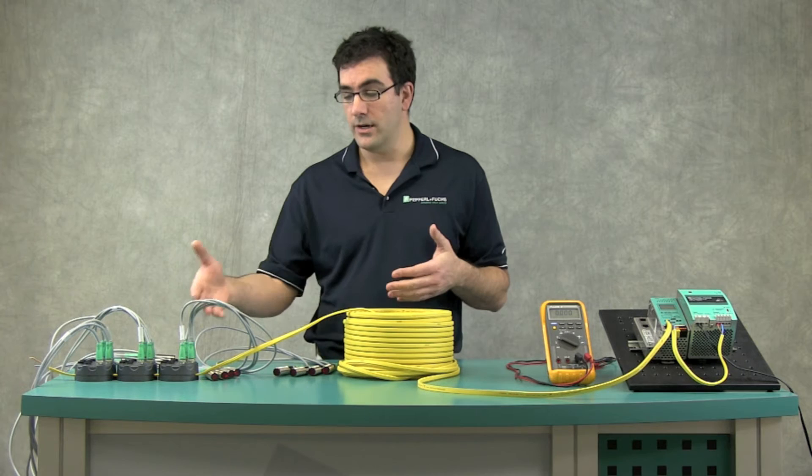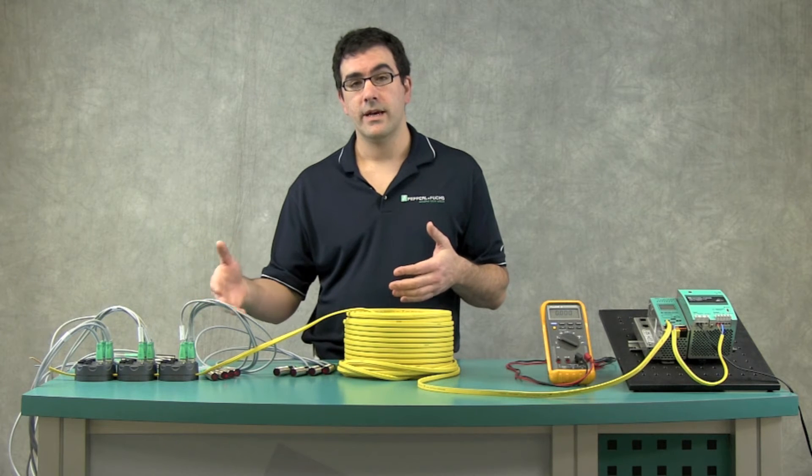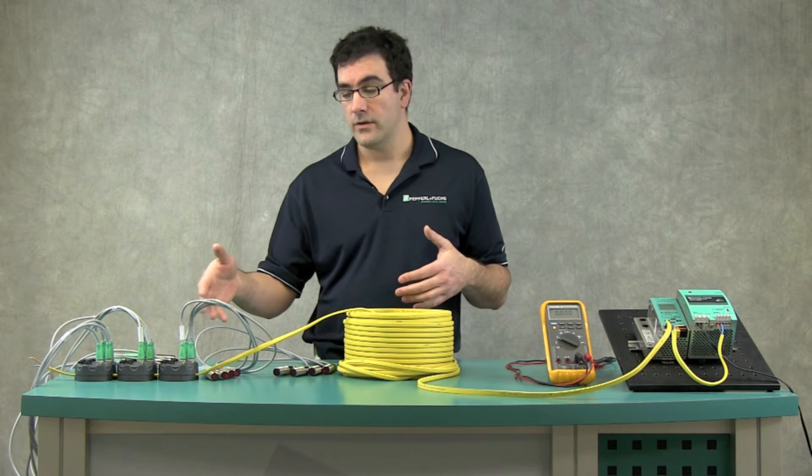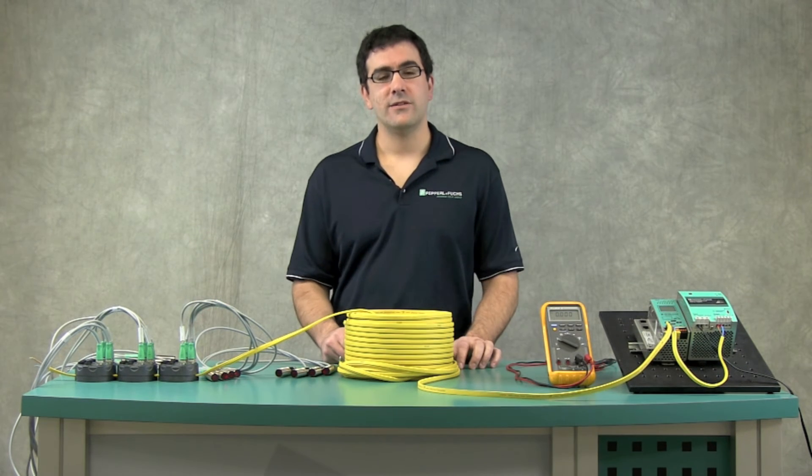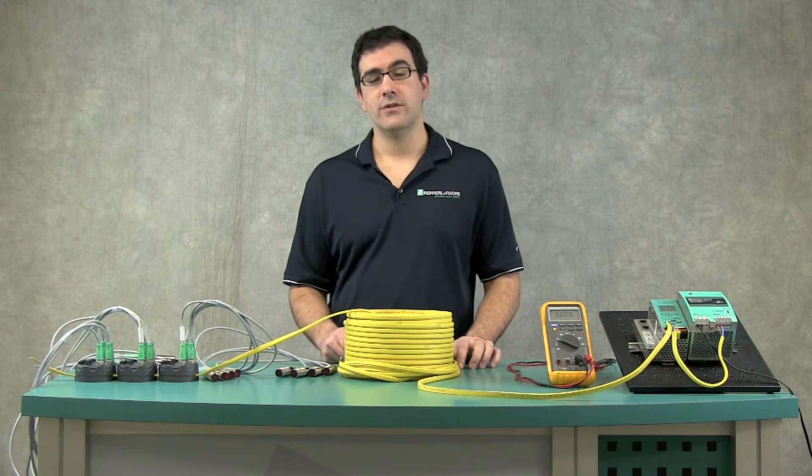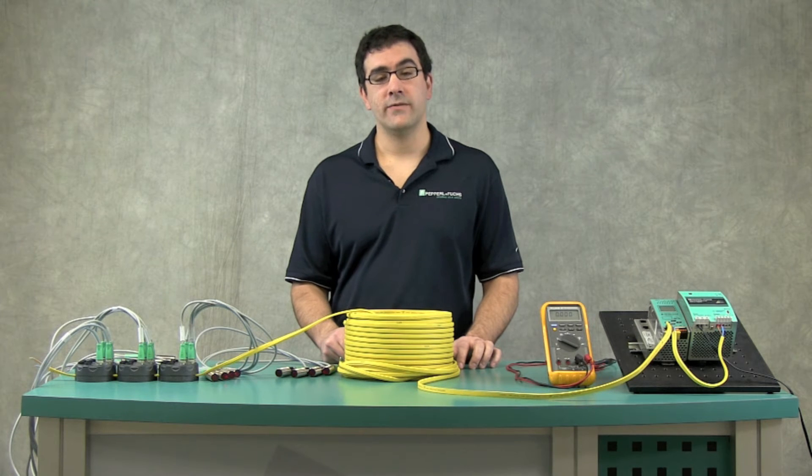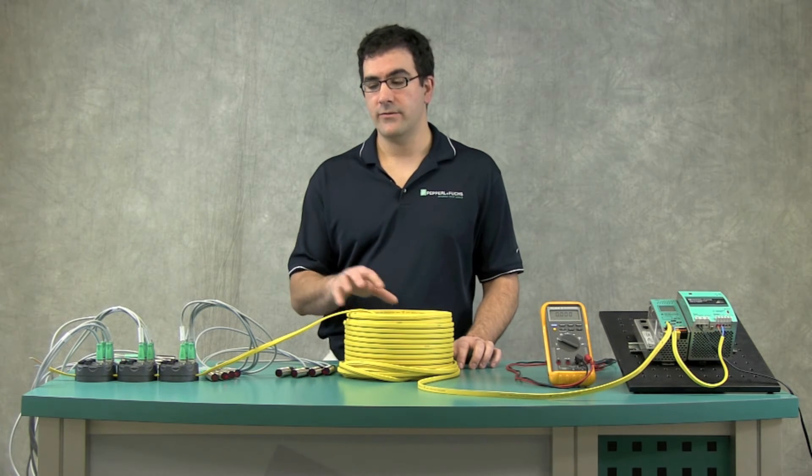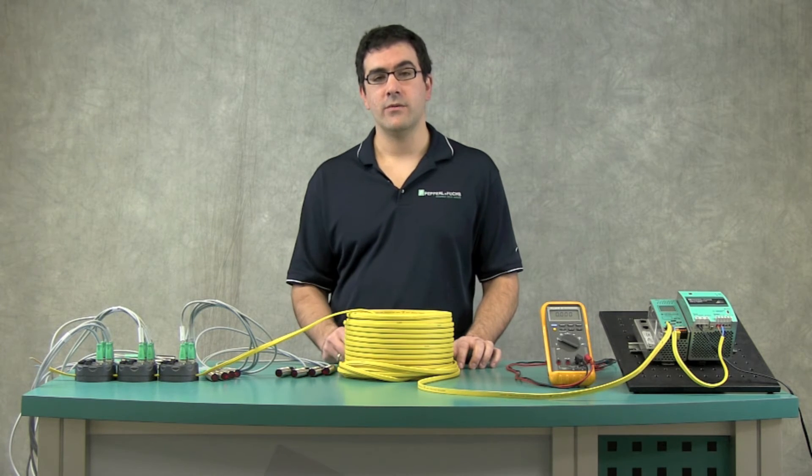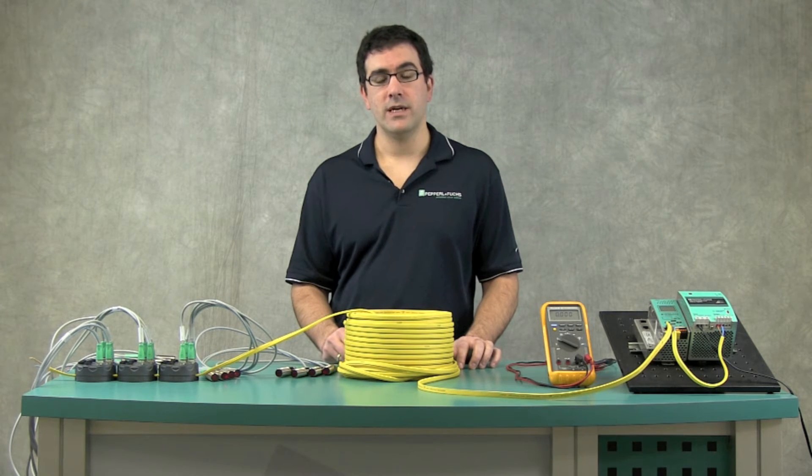You just want to make sure that you're under that 4 volt drop. So now let's look at the Excel sheet, the AS Interface Power Calculator, and see if we can calculate what the voltage drop would be on the network.